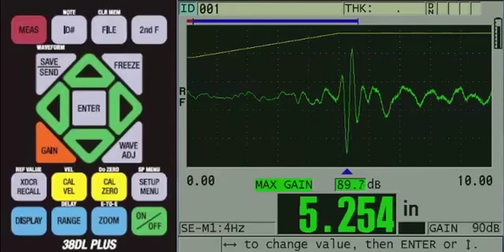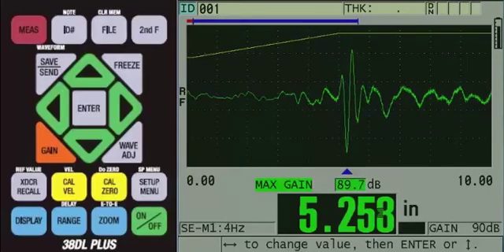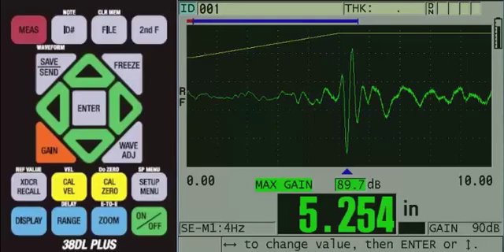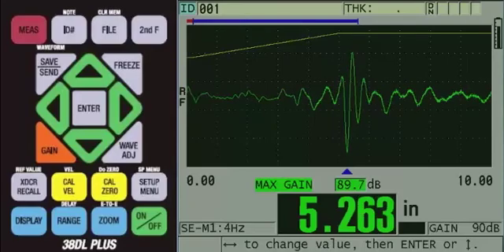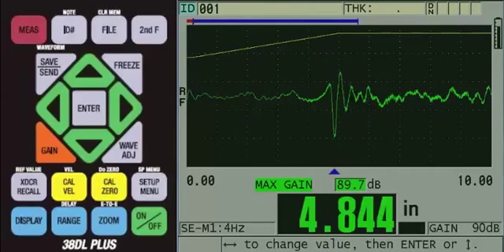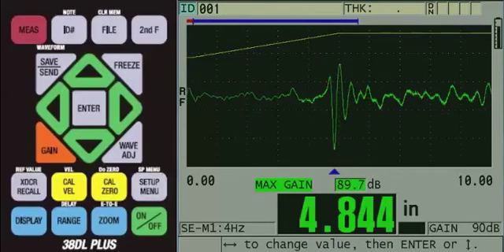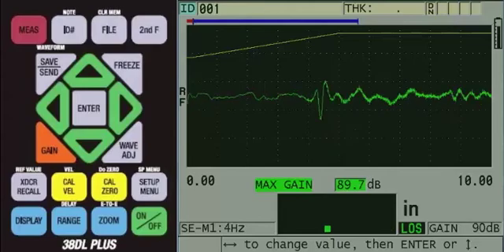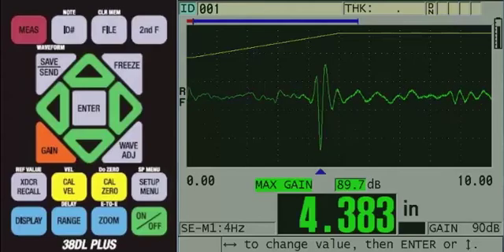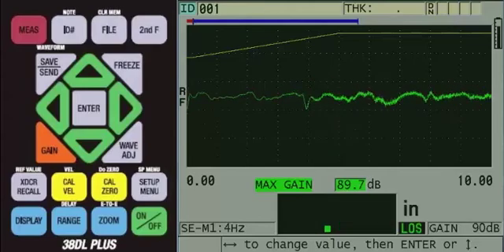Now, we are getting a reading. Before we calibrate, we want to make sure the other steps on the test block are able to be measured. Couple onto each step of the test block to make sure you are able to get a reading.